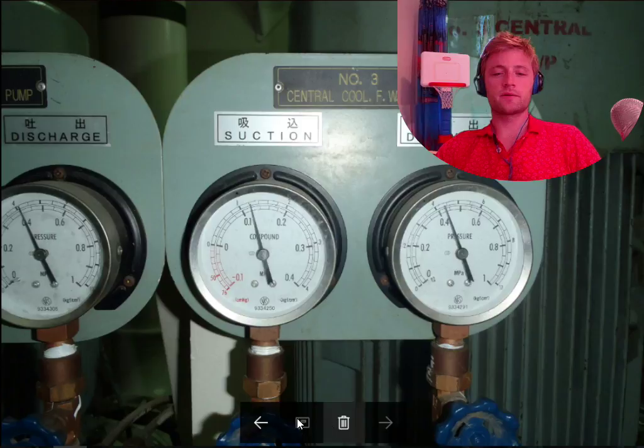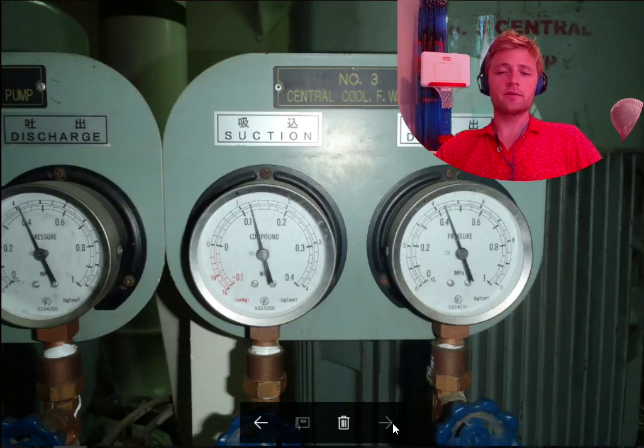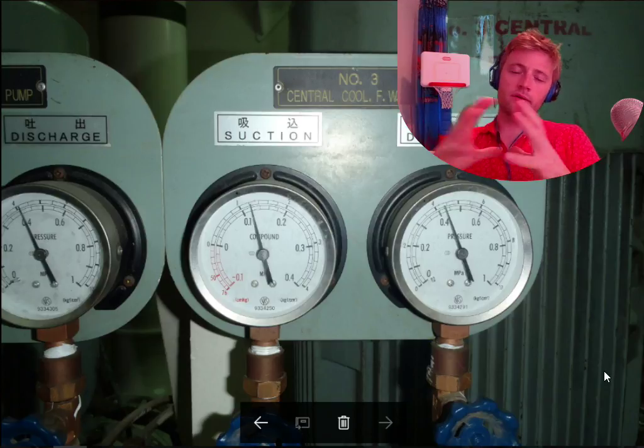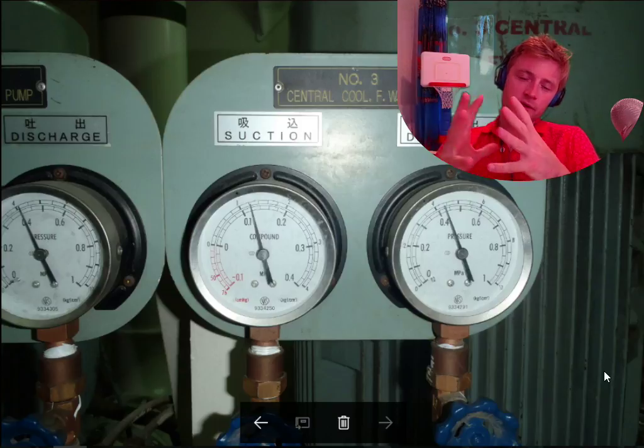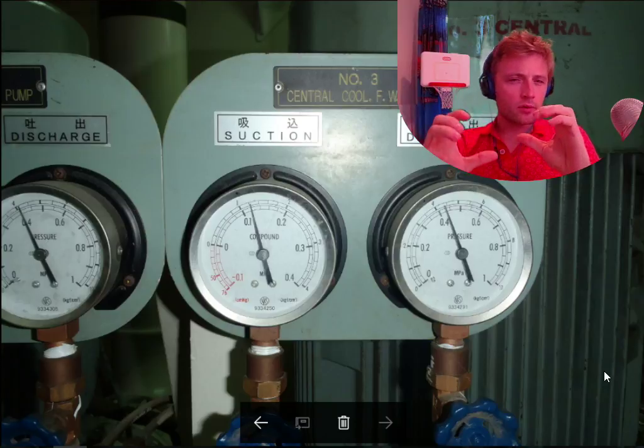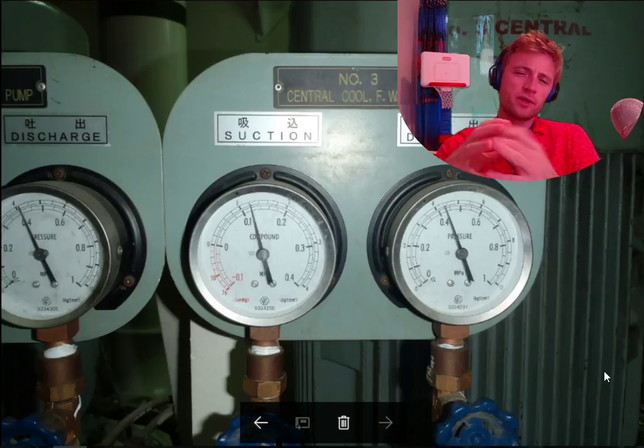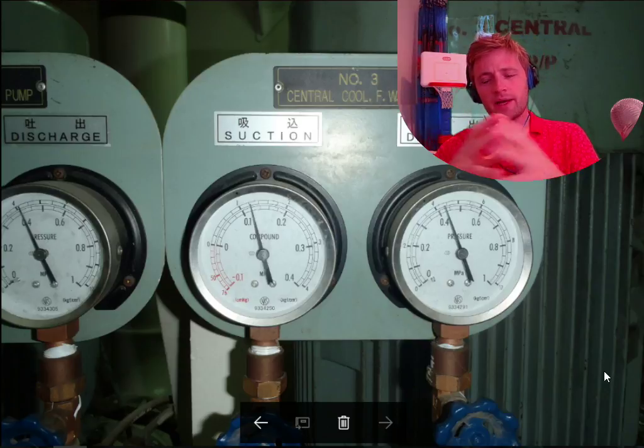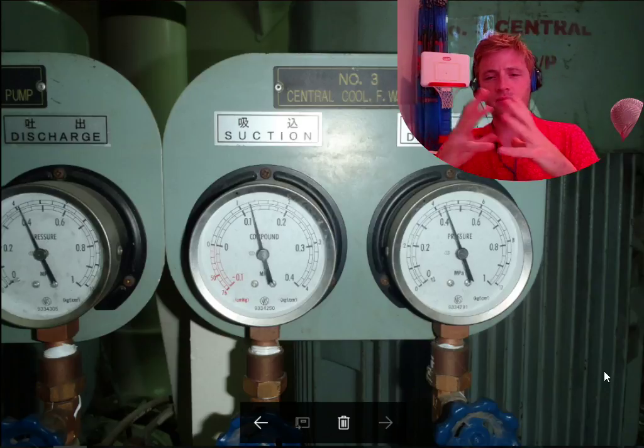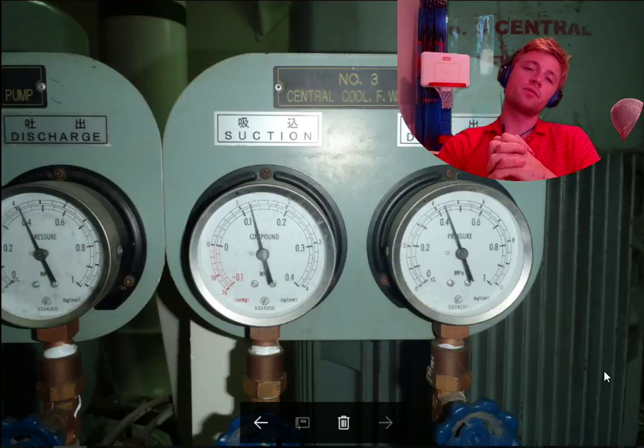This one reads eight kilos — 8.3 — still okay. This is about the gauges. Gauges are located everywhere in the engine room, and you should have one or two spare gauges for each machinery — suction and discharge — so you can easily make a change without any problem, just in case, to check if your machinery is working properly.